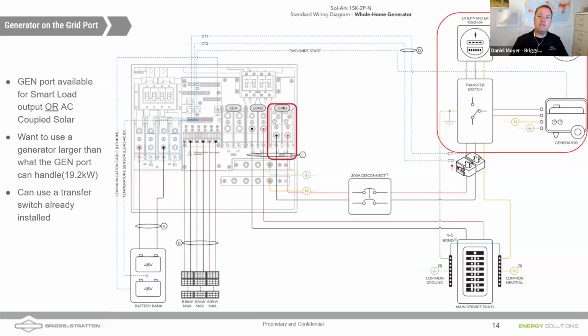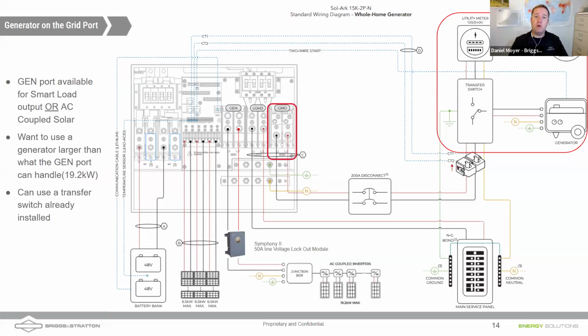Now, Nathan, if we do have AC coupled solar, this is a great example of why we might want to bring in a generator on the grid port. What that allows us to do is free up the gen port. But if we do that, there are some concerns, right? Yeah, so one of the things, Daniel, is when you have AC coupled solar, essentially what happens inside the inverter when it's got an AC source and an additional AC source, like microinverters or AC coupled solar through a string inverter brought in through the gen port, is it essentially parallels those inside, right? And generators are grid forming devices, and AC coupled inverters are grid following. The problem is that when they see the presence of grid and you have enabled grid sell, what can happen is those AC coupled inverters can try to lead the phase of the generator.